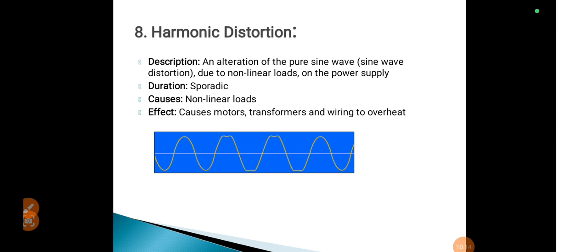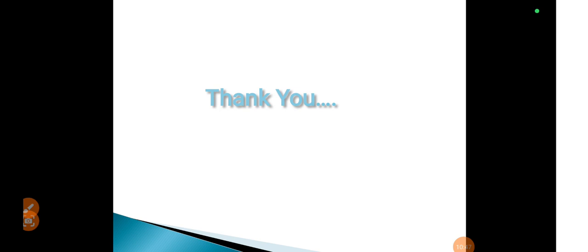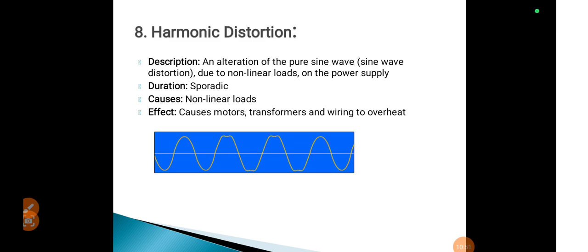The last power quality issue is harmonic distortion. Harmonic distortion means an alteration of the pure sine wave due to non-linear loads on the power supply. The causes of harmonic distortion are non-linear loads and electronics. The effects of harmonic distortion are that it badly affects motors and transformers, and it can overheat transformers, wiring systems, etc. These are the different power quality issues, their description, duration, causes, effects, etc. Thank you.